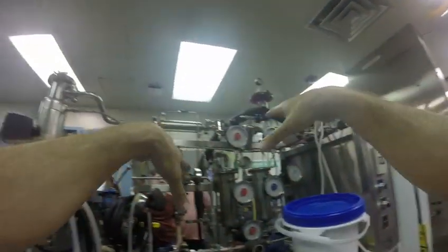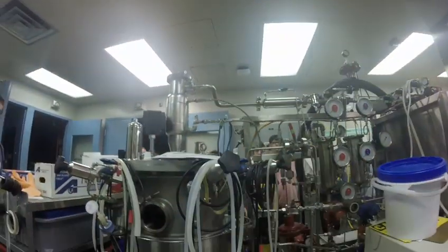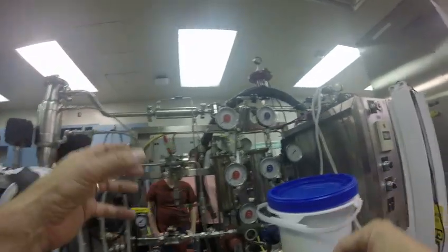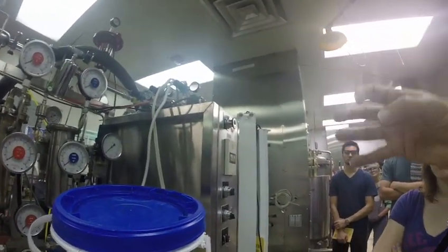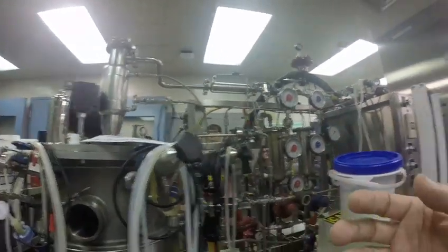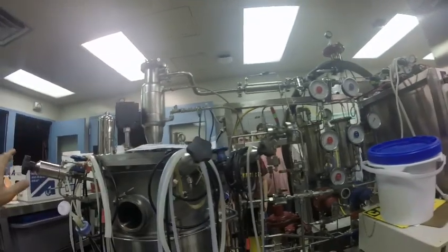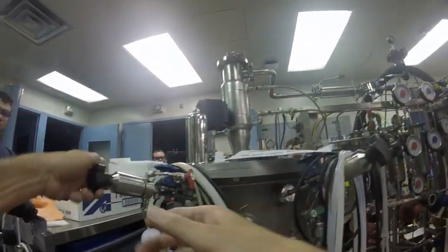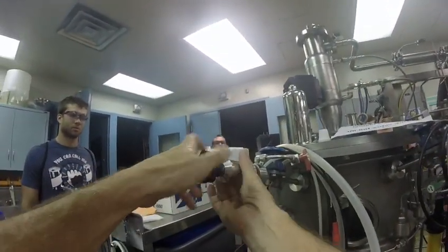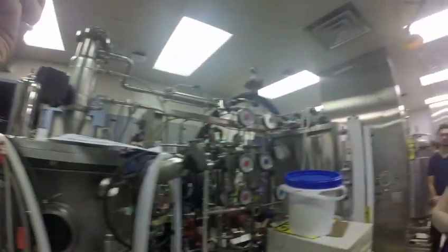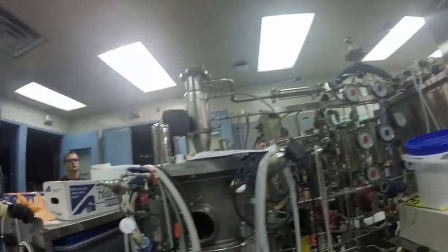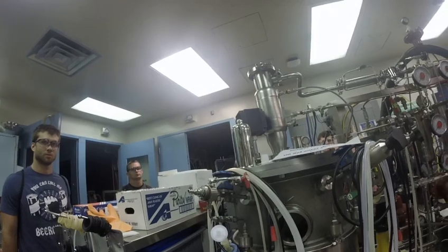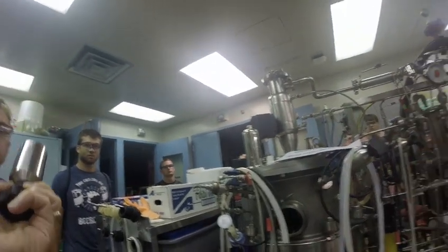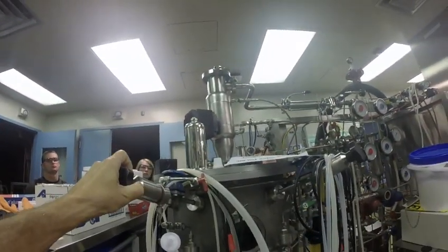And so that's a critical aspect of the design of an aseptic unit like this, is that those steam traps are everywhere after you want to actually do a sterilization. And so if you take a look at a sample port, and I'll be over there in a moment, I'm going to hand it to this group here. Every inlet and outlet of this unit is functionally an autoclave. And so this is like a little mini autoclave.